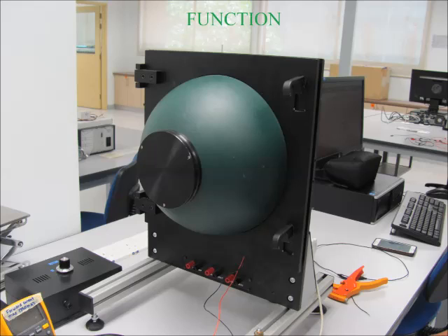It is typically used with some light source and a detector for optical power measurement, such as the Konica Minolta cameras we use in the lab. A few examples of tests which can be carried out by the integrating sphere are: number 1, the total power flux of a light source. Number 2, reflection and absorption of samples. Number 3, to provide a photometric standard by creating a reference radiation source. Number 4, the total light radiated in all directions of the lamp.